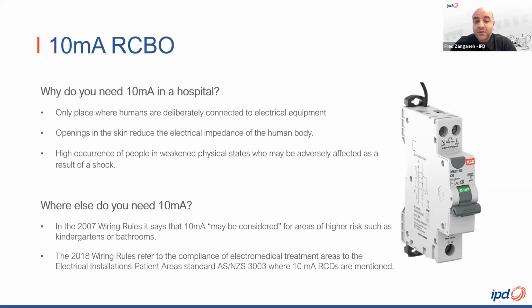Yeah, there are some other areas where we may need to use 10 milliamp RCDs as well. In the 2007 wiring rules, it says that 10 milliamp may be considered for areas of higher risk, such as kindergartens or bathrooms. It's recommended, but it's not mandatory. In section 7 of the current 2018 edition of the wiring rules, electromedical treatment areas need to comply with AS/NZS 3003 Electrical installations, patient areas, where 10 milliamp RCD requirements are mentioned as well. So there is that specific standard now for hospital environments. So it's worthwhile noting, guys.